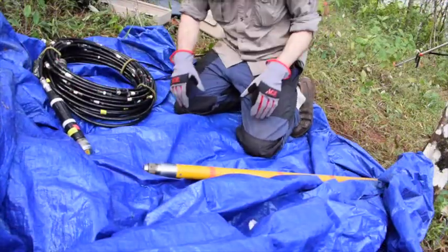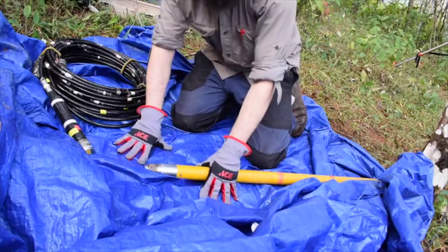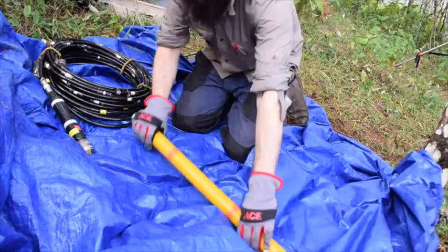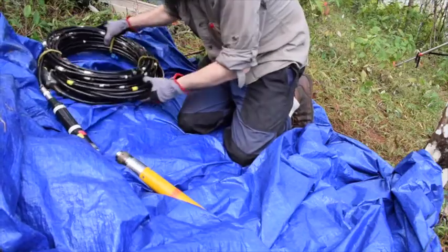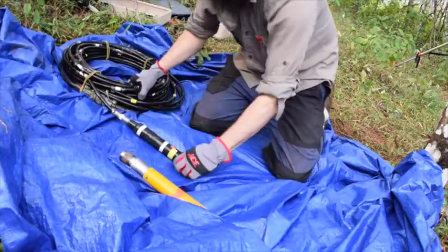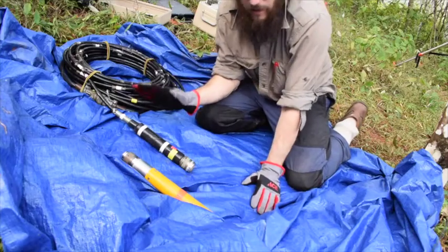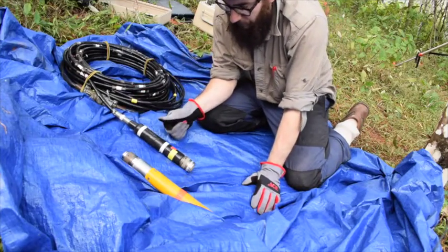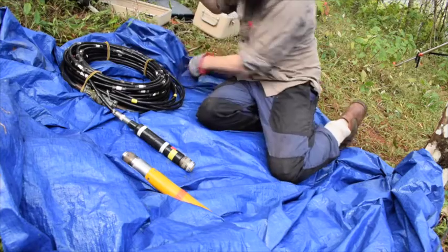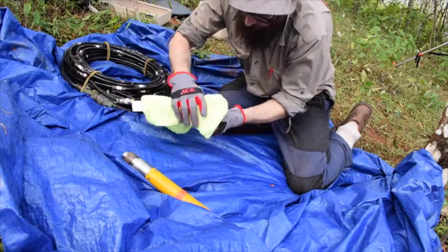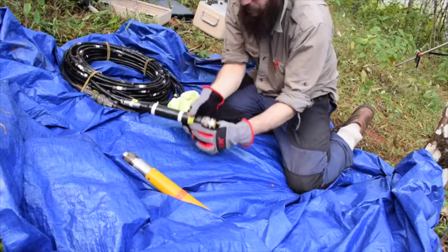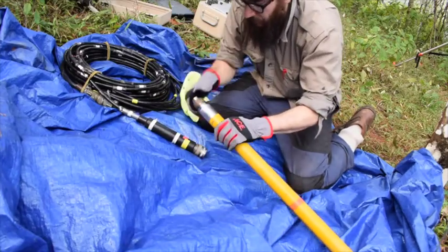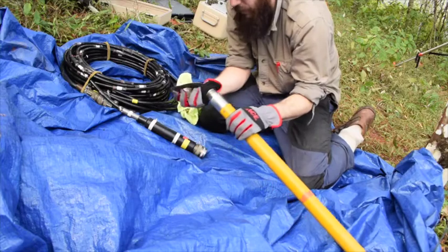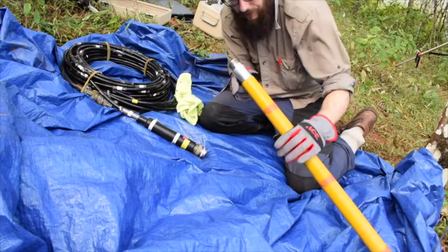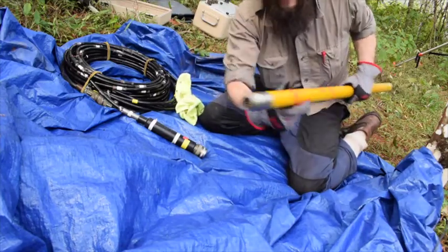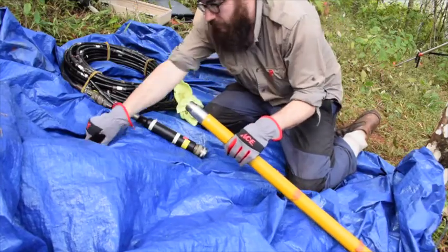So when we do the connection to the probe, the best thing to do is put it down on a tarp if you can, and then just do the entire connection with everything resting on the ground. And that's mostly because this avoids a lot of risk with accidentally torquing the cable head too much. So we'll just make sure there's no dust and debris. You can take off both caps. You want to look in the top of the cable head beforehand. Just make sure there's no dust and debris in there either.